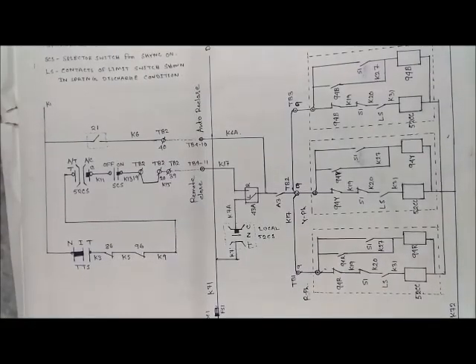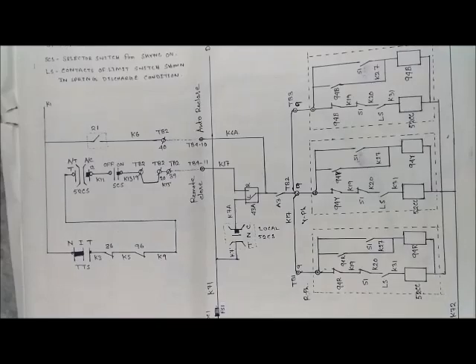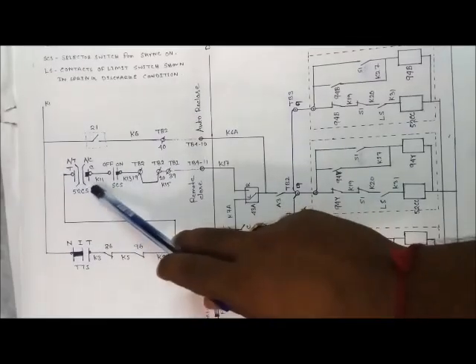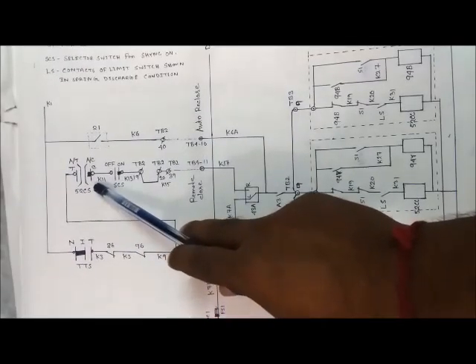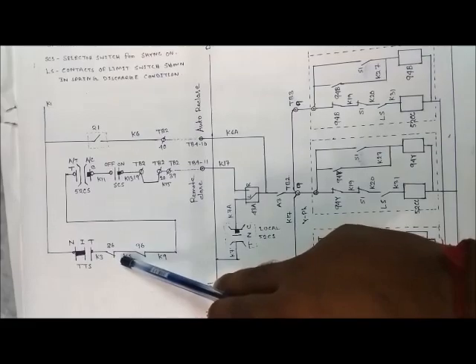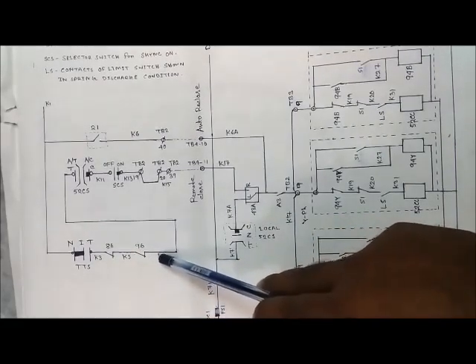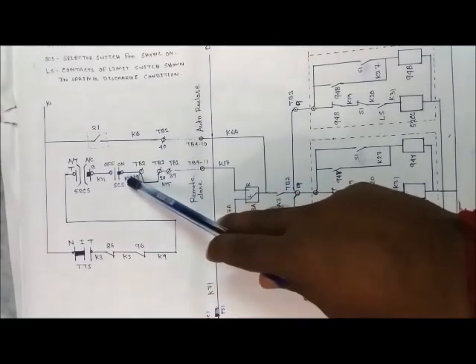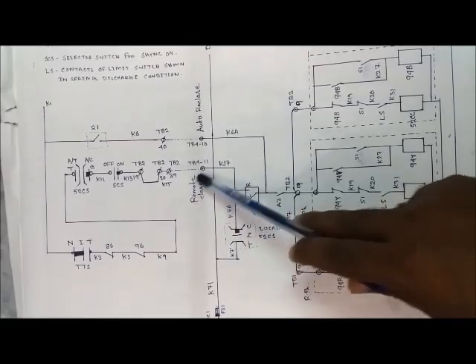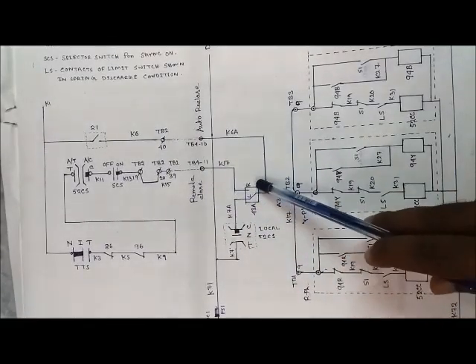For remote closing, the TTS switch position must be in either normal or inter position. Also ensure that the 86 and 96 relays are not in the operated condition. If we give the control pulse from the closing control switch, the positive DC comes through the TTS switch, through the NC contact of the 86 relay, through the NC contact of the 96 relay, through the SCS switch — which must be in the ON position.